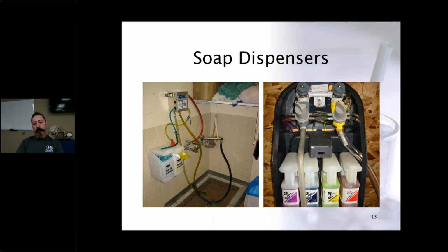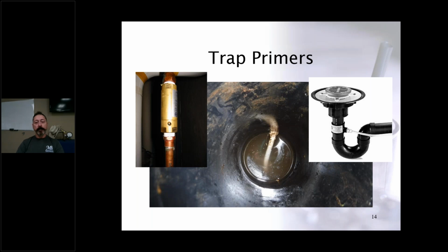And so they are, again, connected to the drinking water supply and sometimes connected to the janitor sinks, and they add to some confusion with that as well. Trap primers are a cross connection where you've got a water supply that feeds into a floor trap primer. This keeps the sewer smell from coming up into a room by adding water to it. So that is a cross connection that is a severe hazard because it's connected to the sewer system. That's what it looks like on the other end inside the trap primer, but it is a very common cross connection in commercial buildings or in some homes, and in floor drains in bathrooms and so on and so forth.